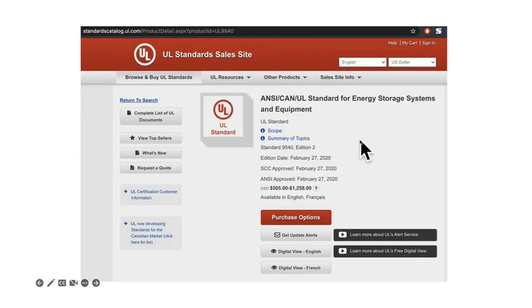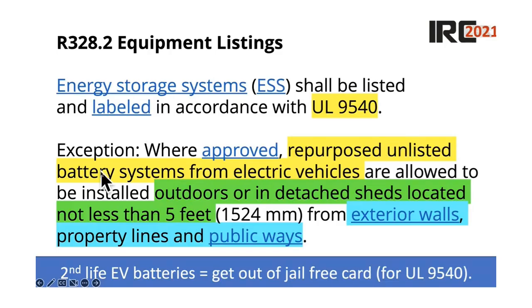I kind of already mentioned some of that stuff. Here is 9540. We already kind of looked at that. That's UL 9540. And here's another interesting exception. Where approved, repurposed unlisted battery systems from electric vehicles are allowed to be installed outdoors or in detached sheds located not less than 5 feet from exterior walls, property lines, and public ways. It's sort of like a get out of jail free card for second life EV batteries.